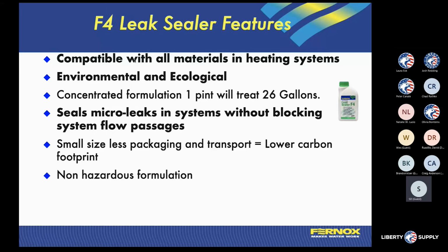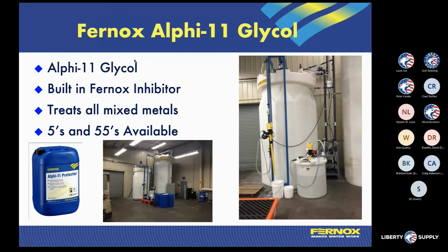Obviously, if you have a leaking system and you keep re-entering more water, you get more mineral in, which means more potential buildup in the system. Obviously, more chemical or more F1 has to be put in. So we want to get the system sealed so you can treat that once and have that be your process.